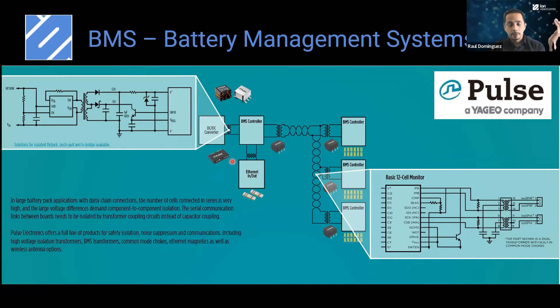So talking more about what the battery management system does is taking care of three primary things. The first one is voltage, because we need to keep the voltage uniform along all the battery and balanced. So we need to equalize the charge between the cells. It's very important. If not, one cell will degrade faster than the other, and at the end this will reduce our capacity in our battery.